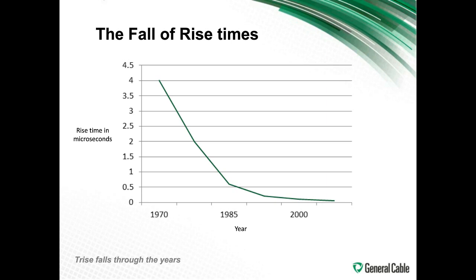And then another evil is, although it's a good quality for the manufacturing process, you have a fall in rise times. Over the years, with the improved efficiency of the IGBT transistors, we have made a very short time for the voltage spike to go up. So that fall in rise time is detrimental to the system, and I'll explain why later, but it's an excellent feature that the new IGBT semiconductors provide.